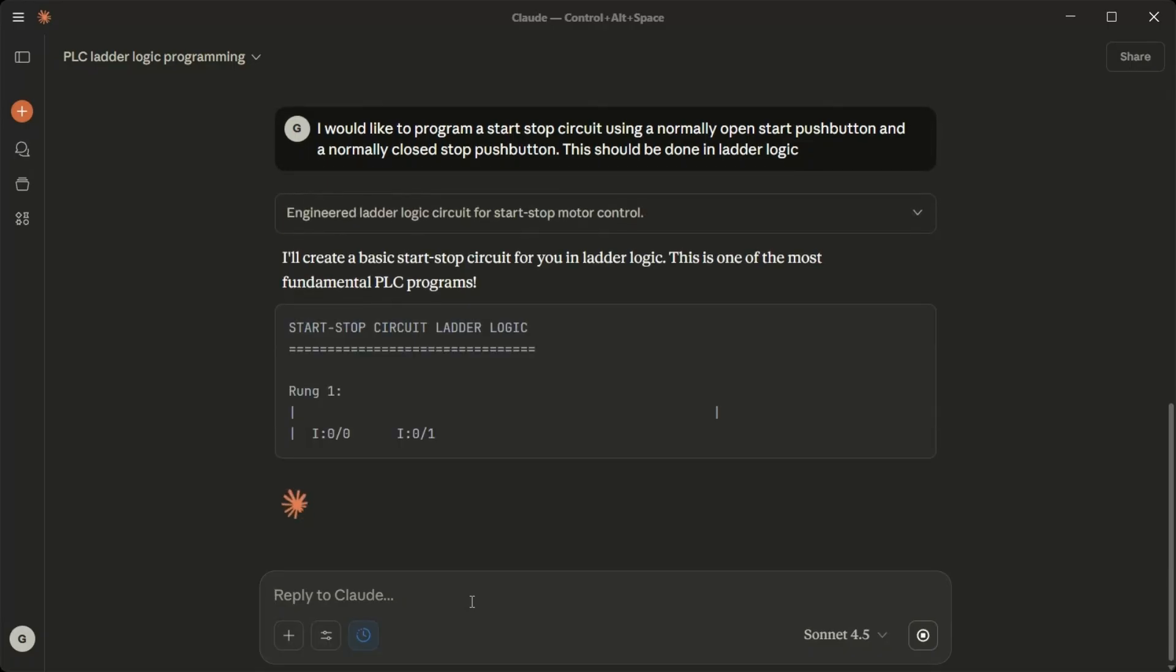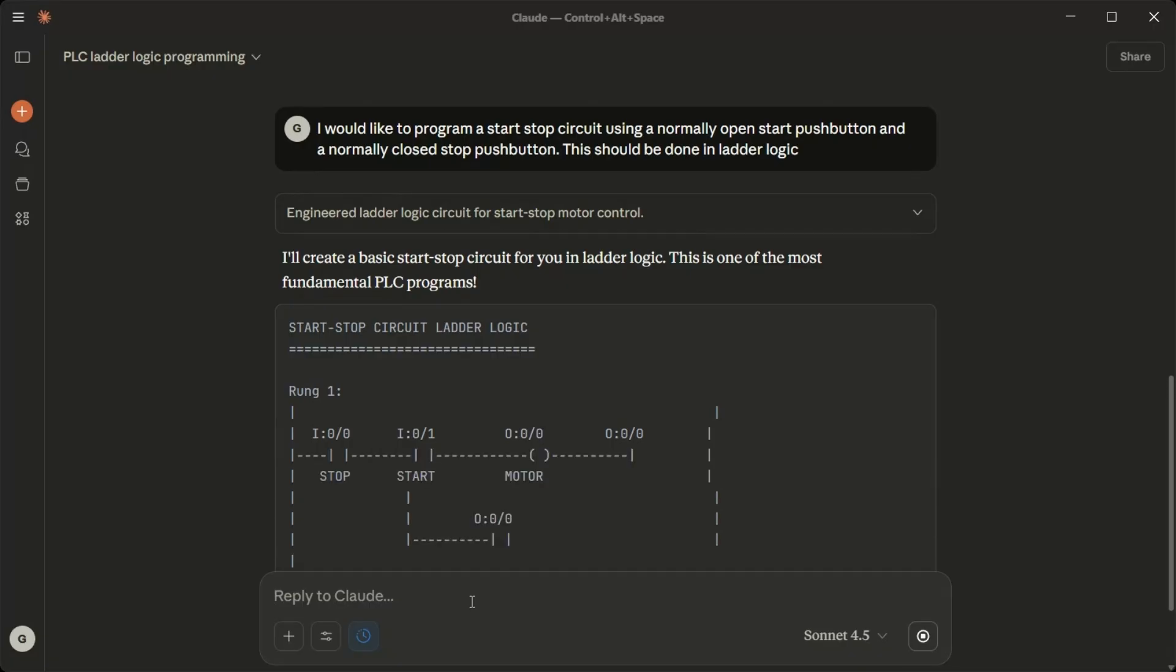How it works at rest: The stop button NC is closed, start button is open and the motor is off. Starting: When you press the start button I0/1, current flows through the closed stop contact and the now closed start contact to energize the motor output O0/0.